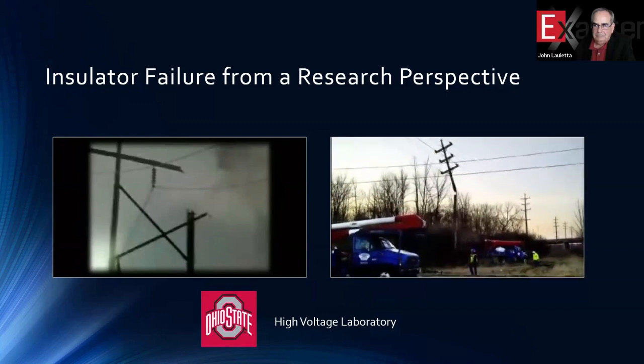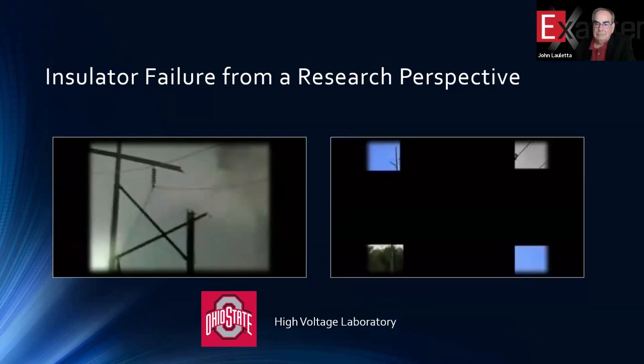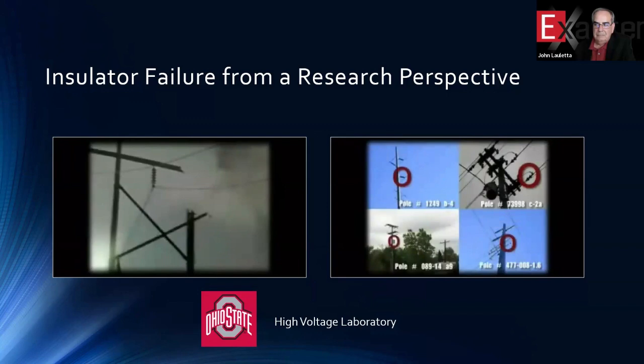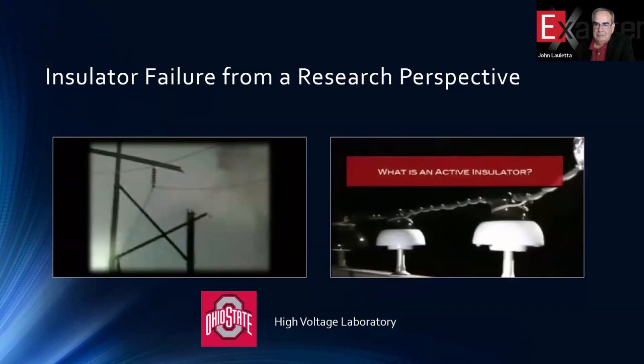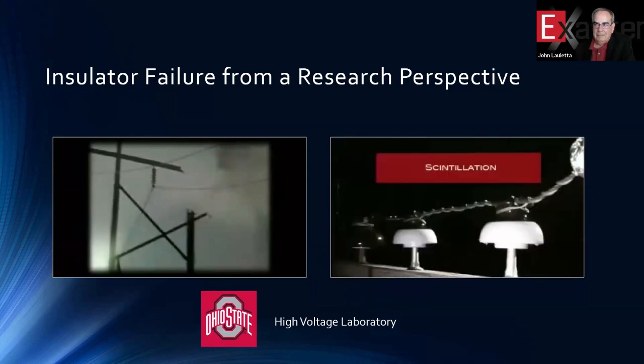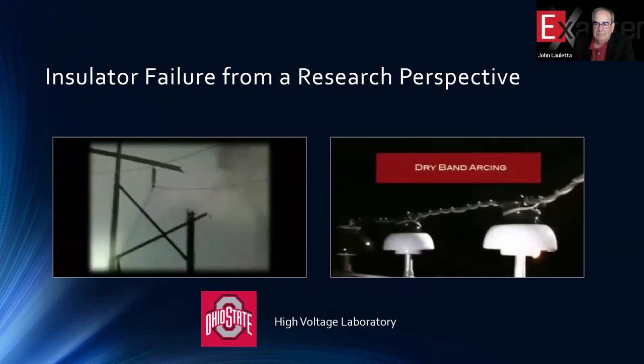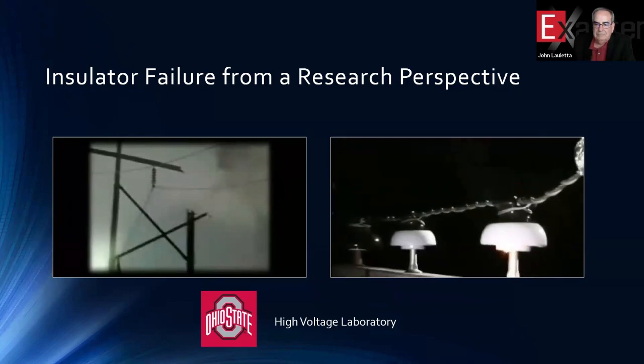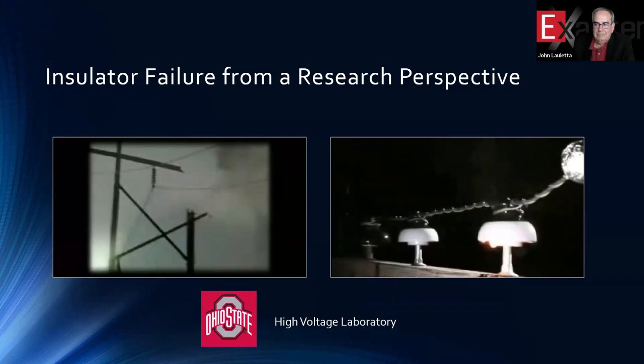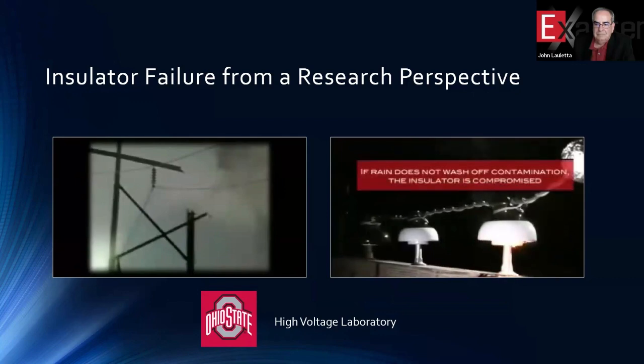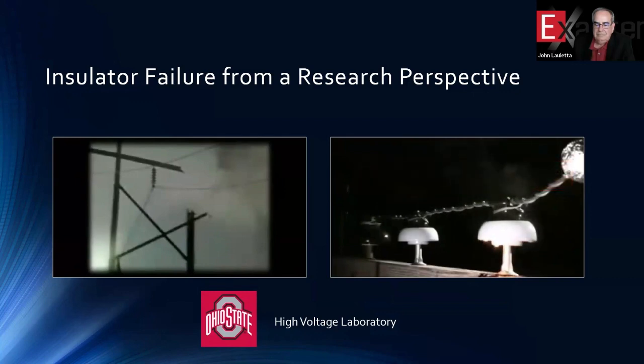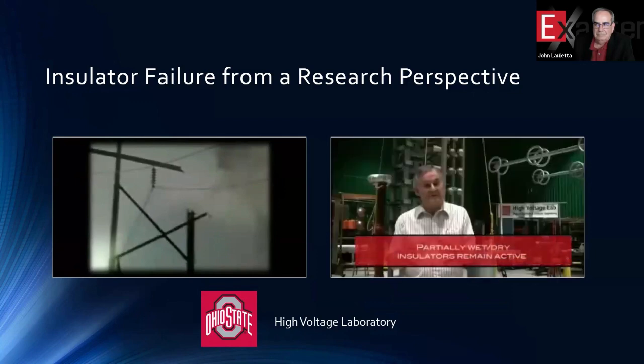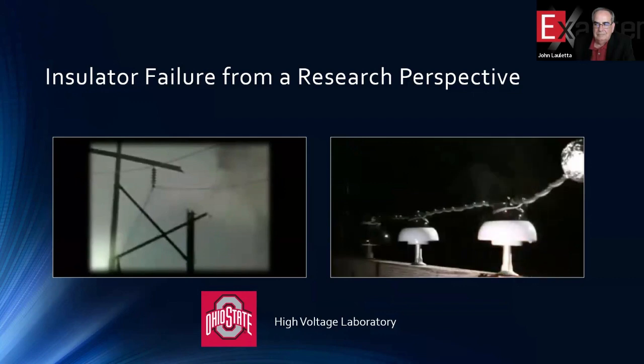I'm not a utility engineer, but I would say that if I would be one, then I would look for a meter that would show which are the active insulators. So what determines an active insulator? Where you have scintillation, partial discharges, dry band arcing on the insulator most of the time. So if an insulator is contaminated, not cleaned, rain was not able to wash it off, then you would have significant durations of time when the insulator is active. When it is drying out after rainy periods, then the insulator, which is close to that contamination flashover, would remain active. When it is completely dry, then you won't find these signs at all.